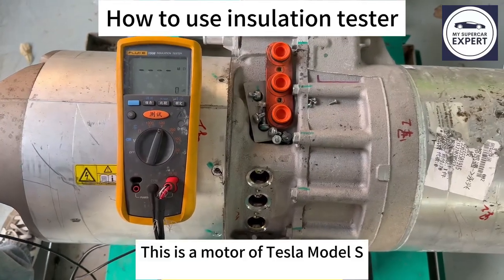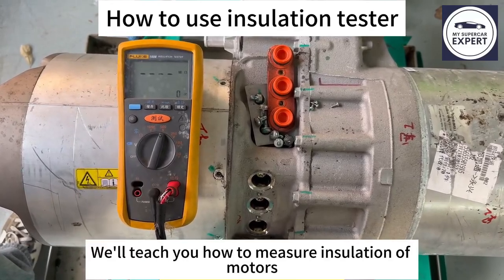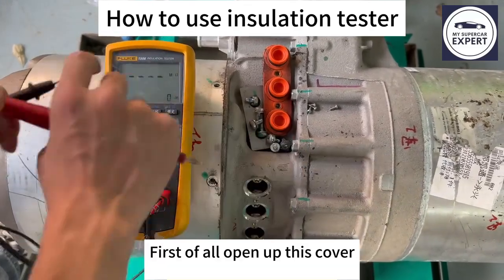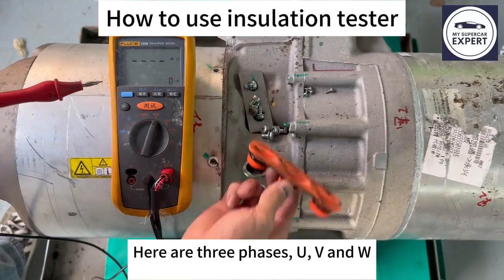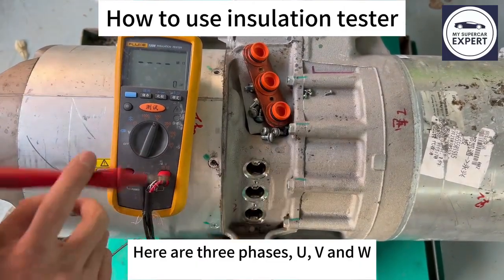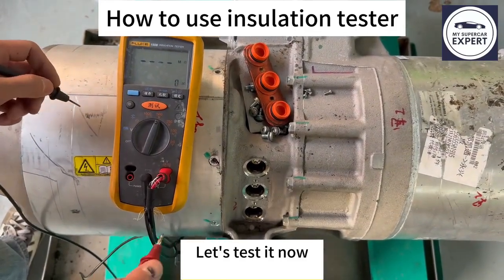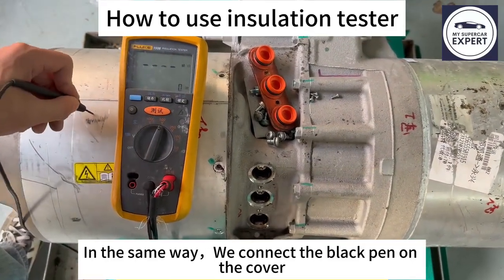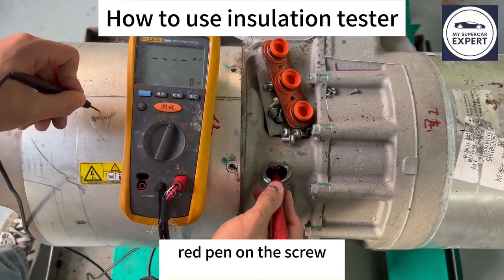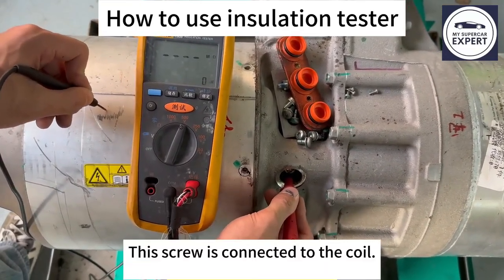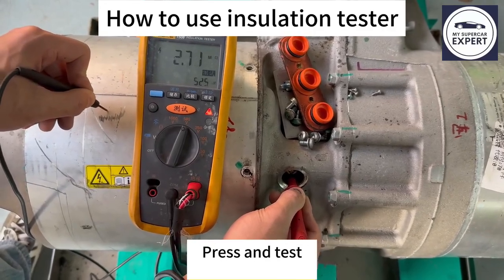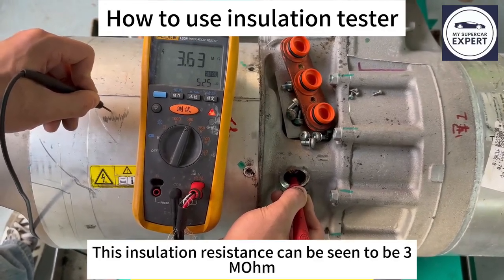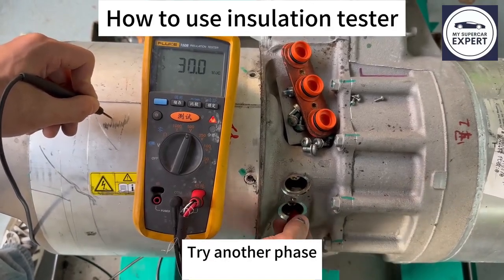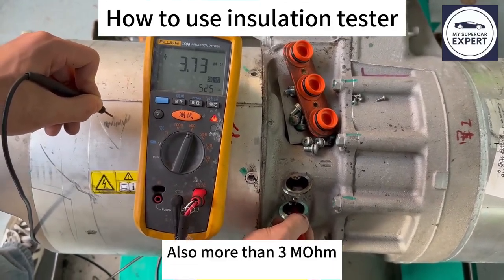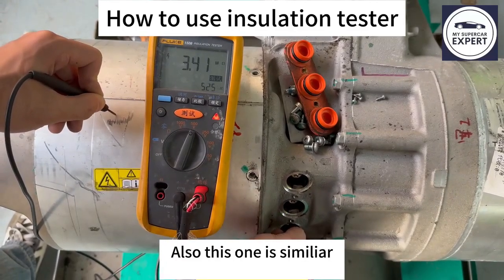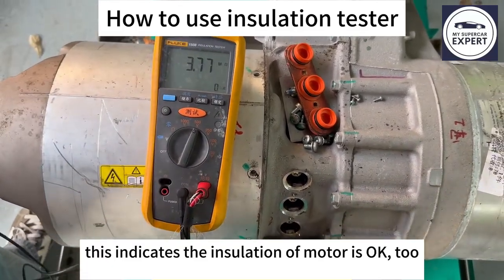This is a motor of a Tesla Model S. We'll teach you how to measure insulation of motors. First of all, open up this cover. Here are three phases, U, V, and W. Let's test it now. In the same way, we connect the black pen on the cover and the red pen on the screw. This screw is connected to the coil. Press and test. This insulation resistance can be seen to be 3 megaohm. Try another phase. Also more than 3 megaohm. This one is similar. This indicates the insulation of the motor is okay, too.